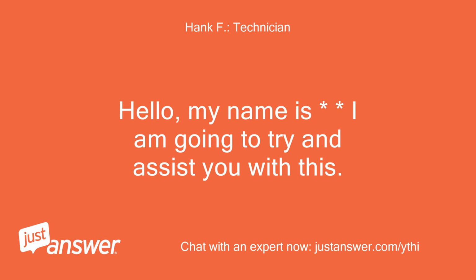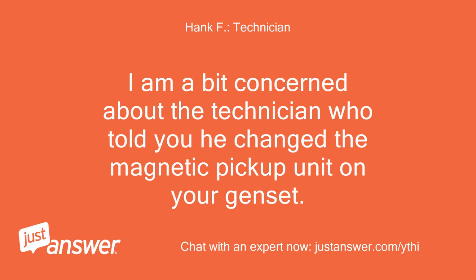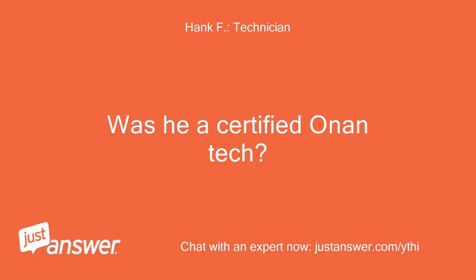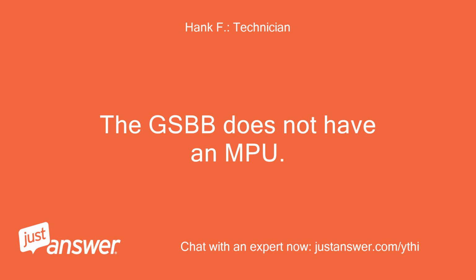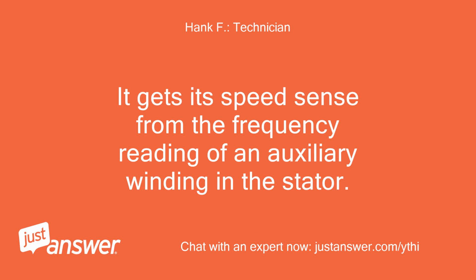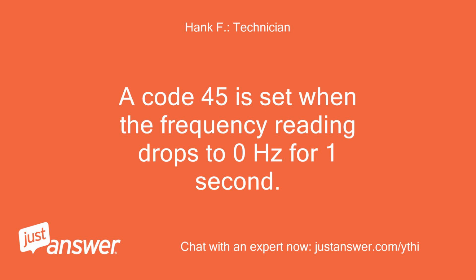Hello, I am going to try and assist you with this. I am a bit concerned about the technician who told you he changed the magnetic pickup unit on your genset. Was he a certified Onan tech? The GSBB does not have an MPU. It gets its speed sense from the frequency reading of an auxiliary winding in the stator. A code 45 is set when the frequency reading drops to 0 Hz for 1 second.